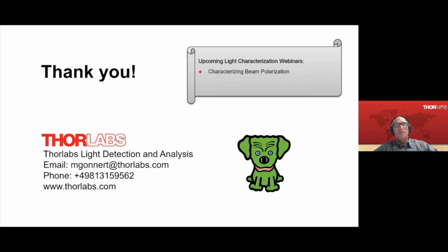So the most important thing here is that you have your focus in a spot where you can go a bit before the Rayleigh length and a bit after the Rayleigh length. So it really depends on the laser that needs to be measured. I cannot answer this from the spot. We would have to come back to this question.